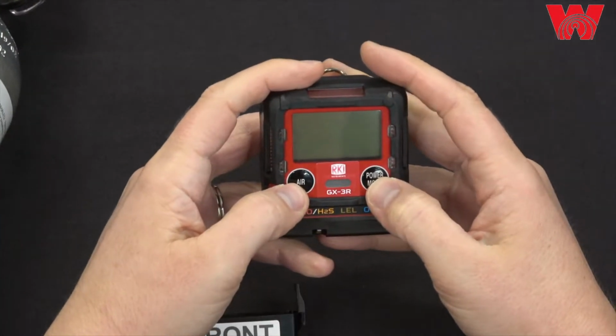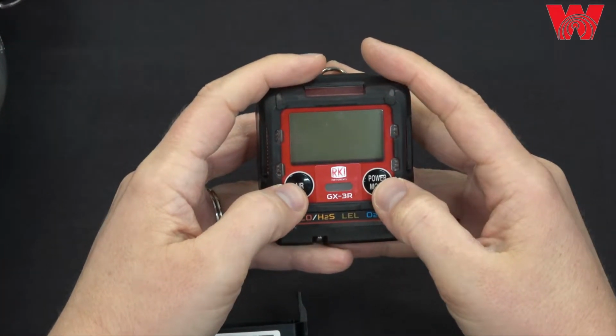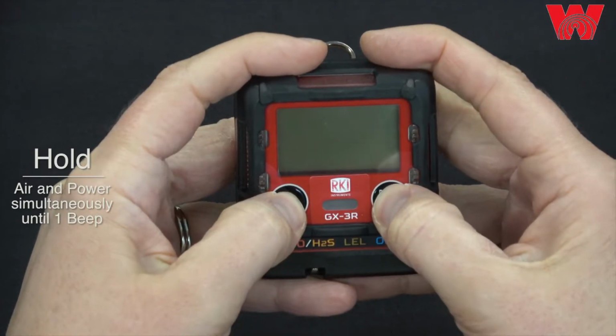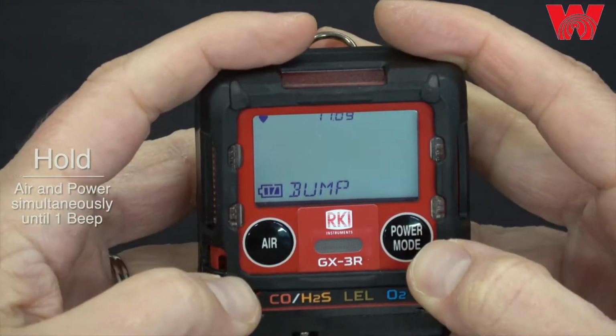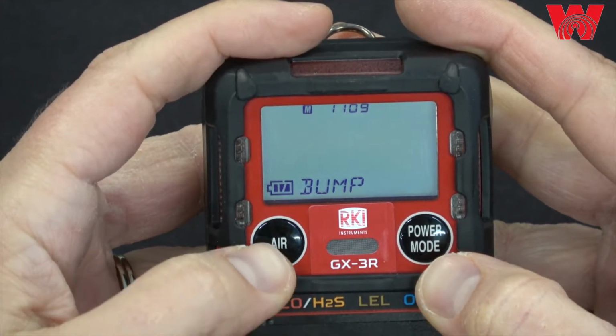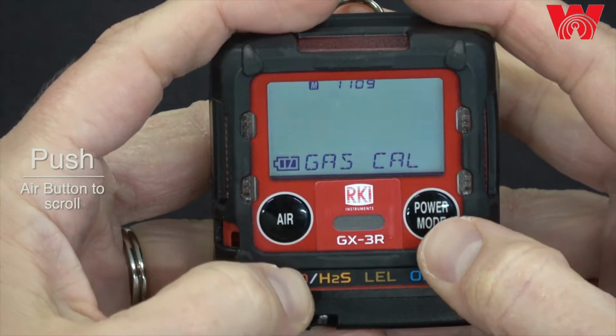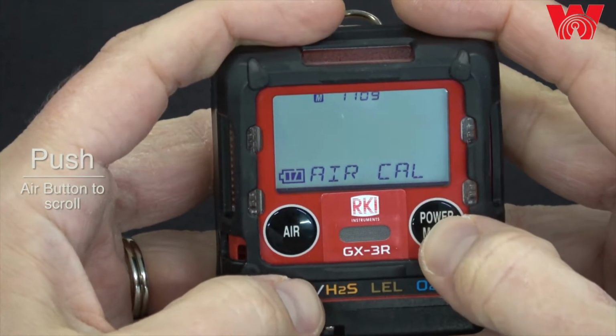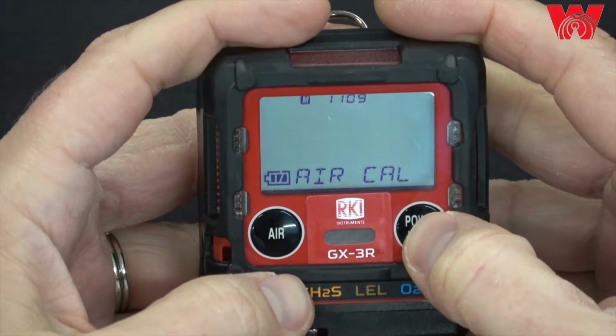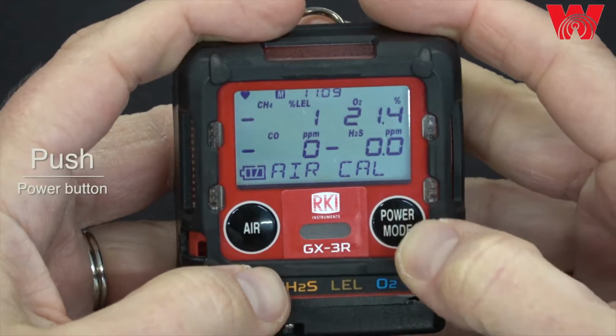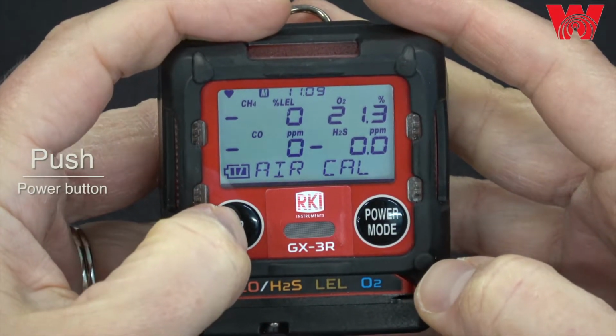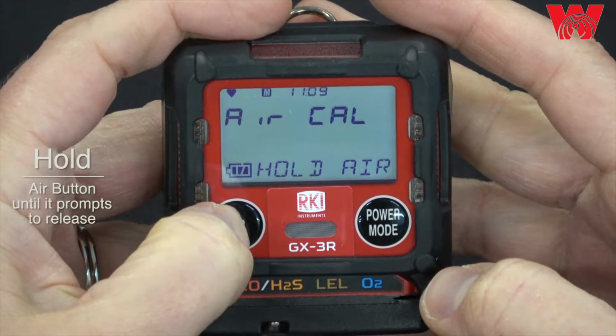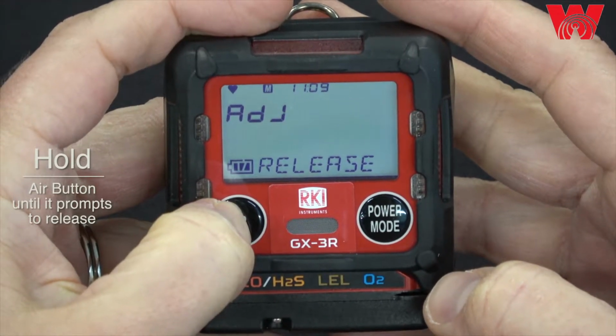To get into the calibration, you need to get into user mode. Hold air and power mode at the same time, and release when you hear one beep. Use air to scroll to gas cal. We're going to do an air cal first, so I'm going to press power mode, and then I'm going to hold air until the instrument prompts me to release it.